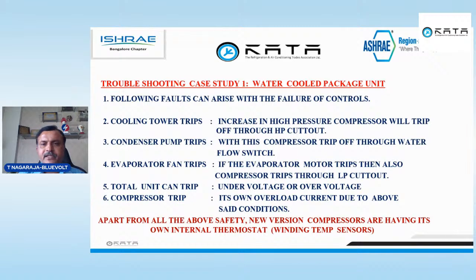Cooling tower trips, why? An increase in pressure will trip the compressor off through the HP cutout if the cooling tower trips. If the condenser pump trips, the compressor trips off through the water flow switch. If the evaporator fan or motor trips, then the compressor also trips through the LP cutout. The total unit can trip on under voltage or over voltage. The compressor trips on its own overload current due to the above conditions. Apart from all these, nowadays all compressors have inbuilt winding temperature sensing. If the motor goes beyond the temperature limit, the compressor itself has a safety.